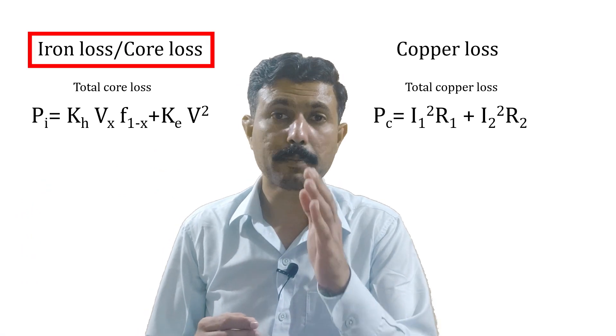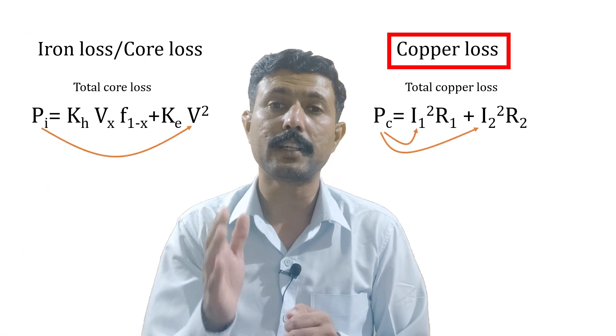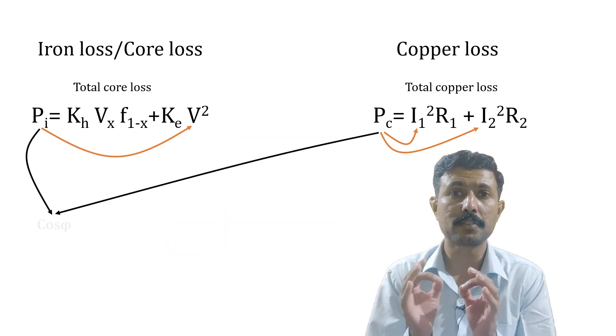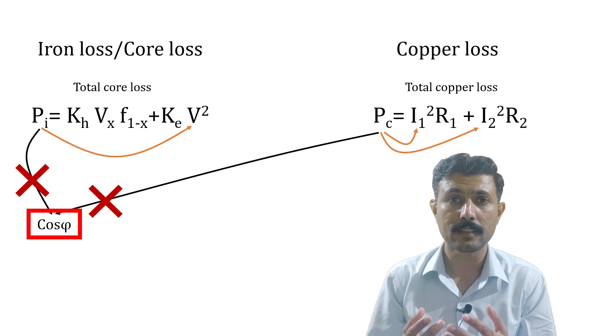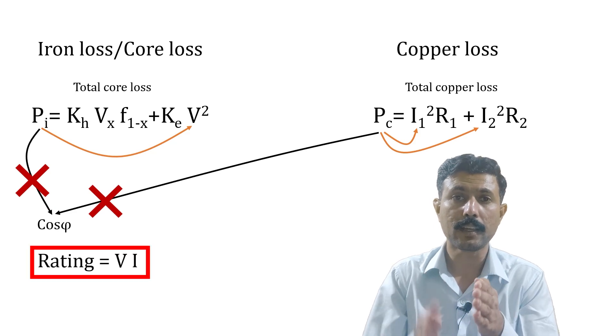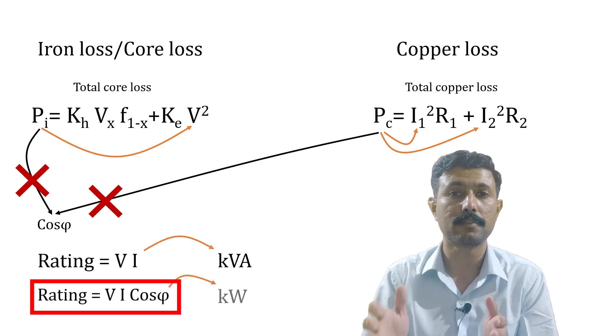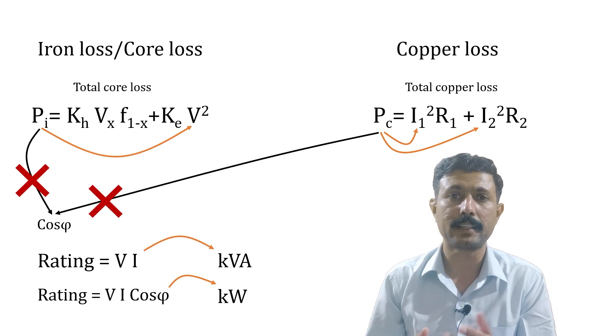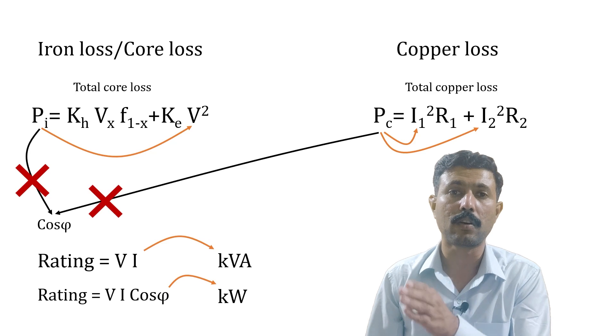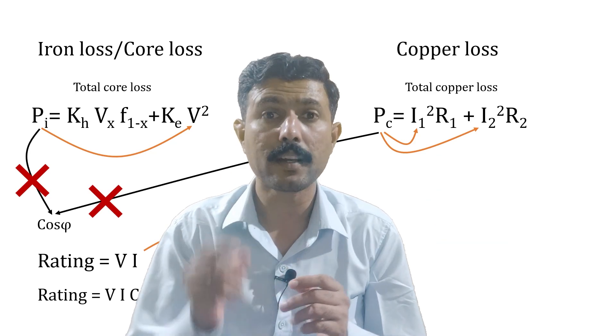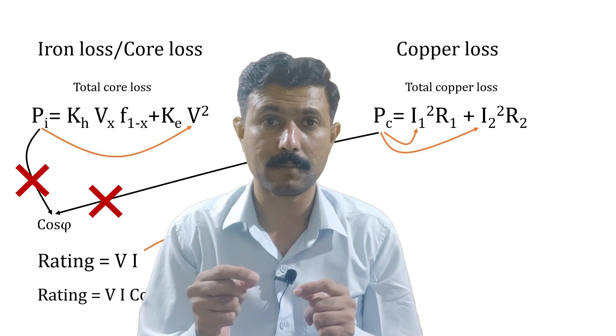There are many ways to understand this, but we are going to explore two of them. Starting with the most common explanation: the iron loss of a transformer depends on voltage, and the copper loss depends on current. Neither of these losses depends on the power factor, and that is why the rating becomes V and I only — not V·I·cos φ. That's why it is VA and not VA·cos φ.